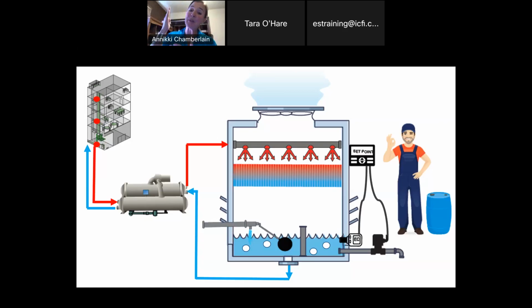What happens if the blowdown valve gets stuck closed? What kind of risk is that? Damage, exactly. Thank you, Allison. Basically, we're going to be cycling up that high concentration water. We're not going to be getting those minerals out of there. And that's when we could potentially suffer what we call a scale event. And honestly, one scale event can be pretty damaging, especially inside the chiller. So, blowdown valve stuck open, stuck closed.